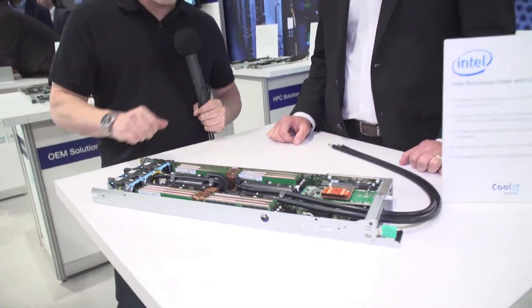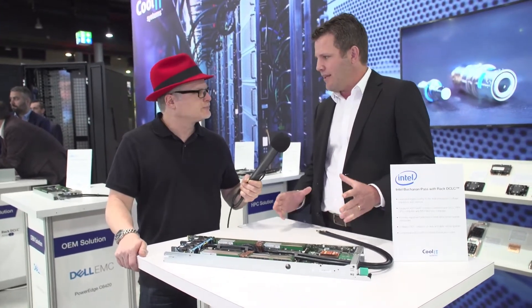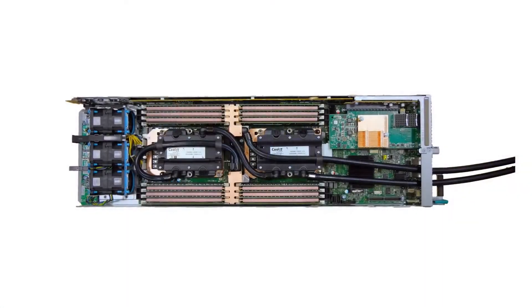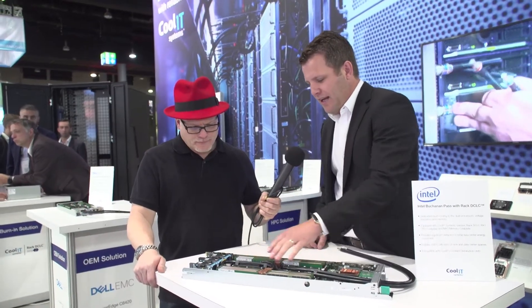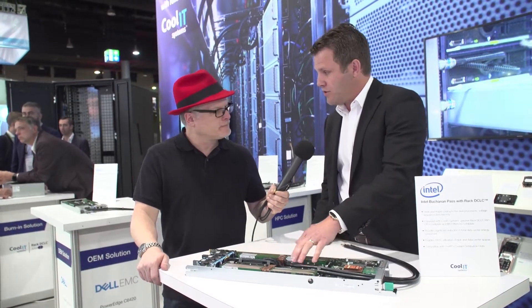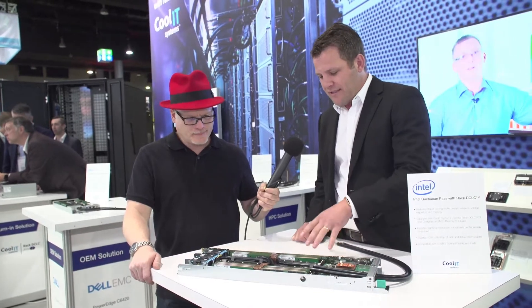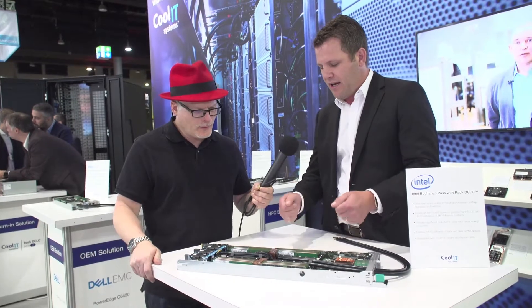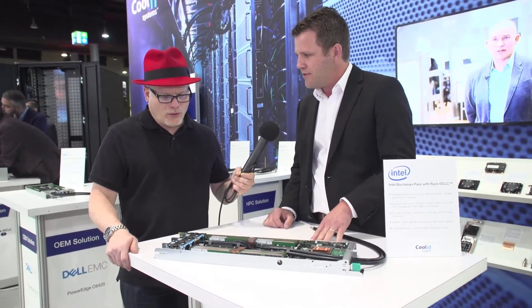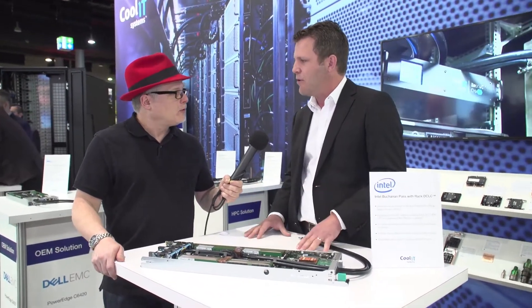This is a different configuration — it's CoolIT's design for the Intel Buchanan Pass server. It's a 2U 4-node server similar to the Dell C6420, but in this configuration we're cooling both the Skylake sockets as well as the voltage regulators from the CPU. All of the DIMMs are also liquid cooled. It's a very unique design where the cold plate stays with the chassis and allows the DIMMs to be removed individually for service. This cools 85% or better of all server energy loads into the liquid path.